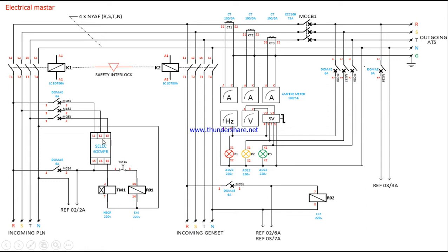The phase failure relay requires three-phase supply R-Y-B. Whenever the R-Y-B supply is available, the phase failure relay connects the common to the NO contact — terminals 15 to 18. Terminal 15 is the common supply of the phase failure relay and terminal 18 is the NO. Whenever supply is available, terminals 15 and 18 are closed. A control MCB from single-phase supply is used; when turned on, it connects to the common supply of the phase failure relay.